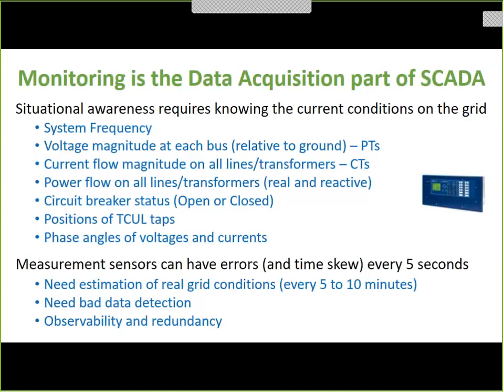Measurement sensors can have errors. You could have a broken sensor. You could have a time skew. To do this stuff, we want everything to be done at exactly the same instant. Otherwise, it doesn't really mean anything. So you have to avoid all time skews. And we're going to do this every 5 seconds. Refresh the SCADA screens every 5 seconds. And then we want to do an estimation of the real grid condition. And we want to do that about every 5 minutes.